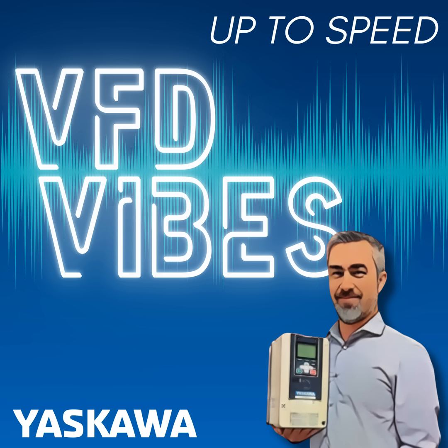I said, you can always keep going upstream. So where does the buck stop? Where typically is your limiting point that you could have the absolute most fault current from? So most buildings, especially factories, something where significant power is required, you're going to have a transformer. It could be outside the building or maybe inside the building, but let's take a typical case where you've got maybe medium voltage at 4160 coming to the input of a transformer, and you've got 480 volt on the output of the transformer feeding all the loads in the factory.